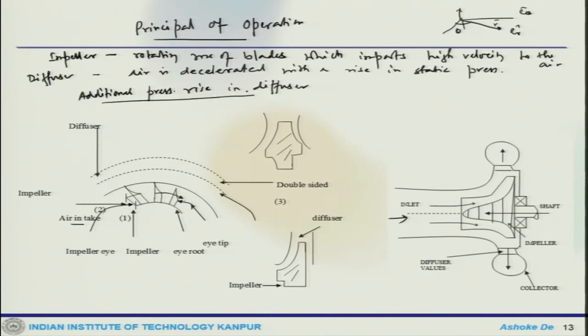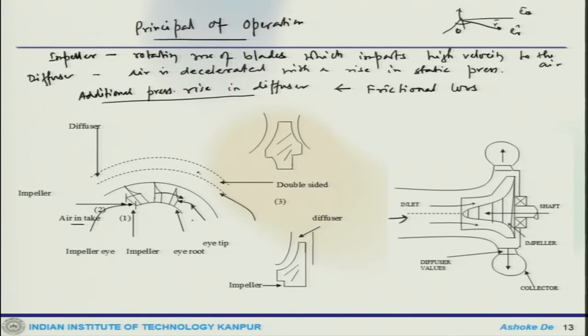One has to take into consideration frictional losses — there will be some loss in stagnation pressure due to friction. In typical design practice, half the pressure rise occurs in the impeller and the other half occurs in the diffuser. At the exit of the impeller, the blades are straight and oriented in the radial direction, which is why the flow predominantly remains radial.